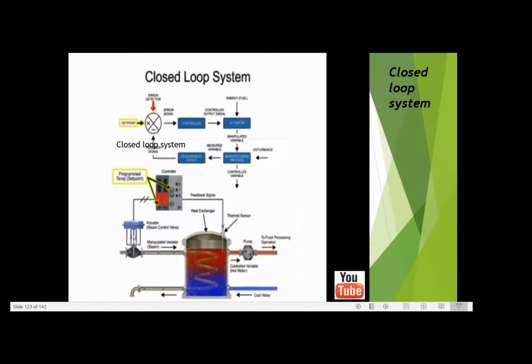Set point is the predetermined value of the desired condition of the control variable. In the heat exchanger, the set point is the programmed value of the water temperature leaving the tank. Error detector compares the set point to the feedback signal and produces an output proportional to the difference between them. Error signal is the output of the error detector. If the feedback signal and set point are equal, the error signal is 0.